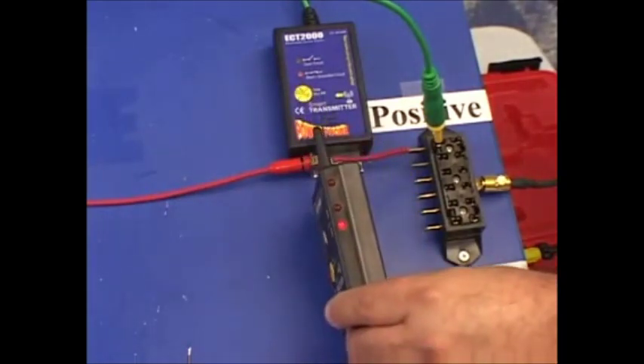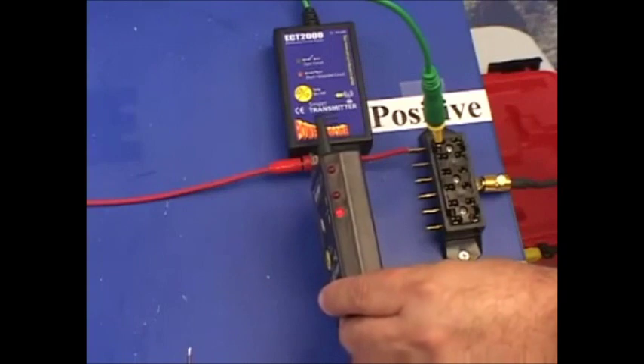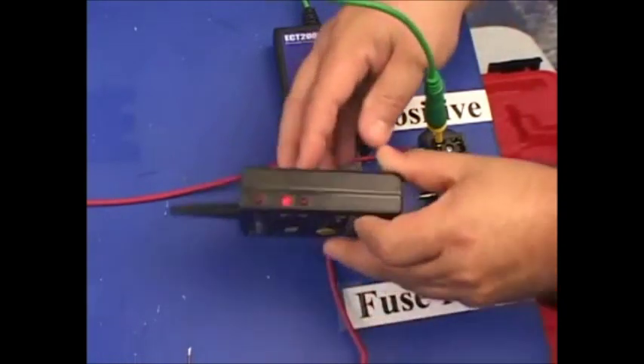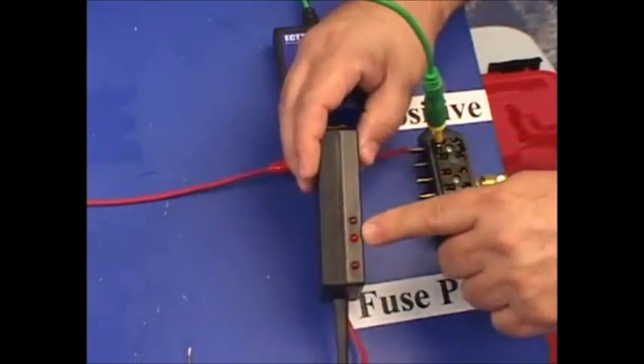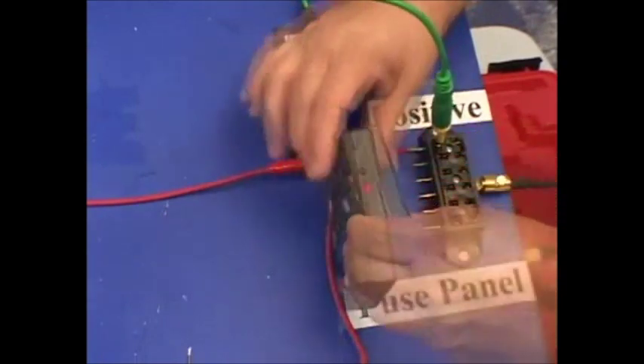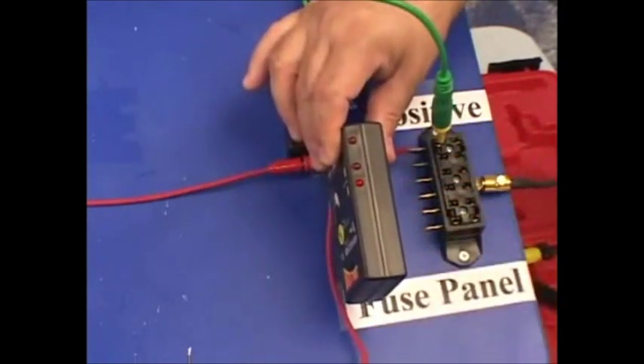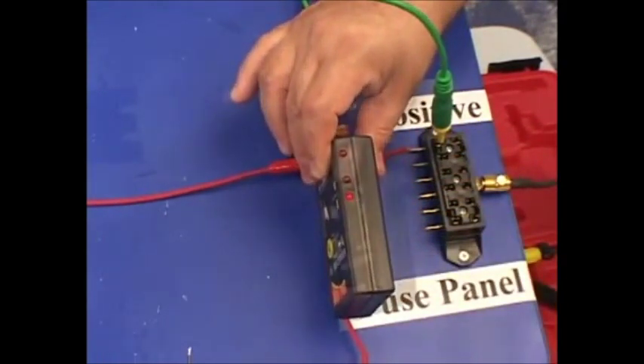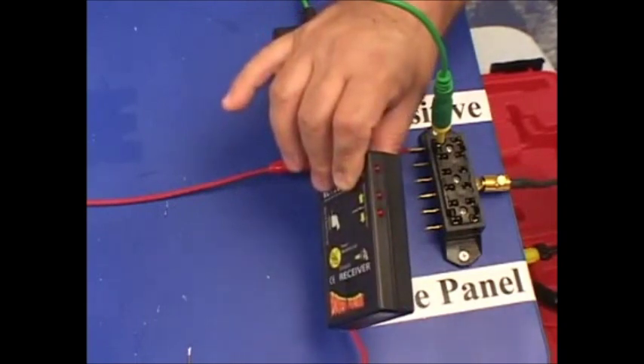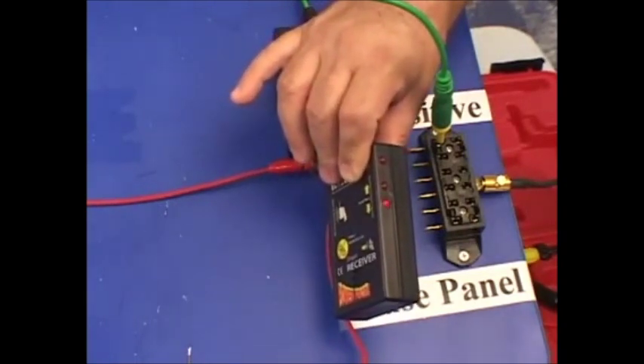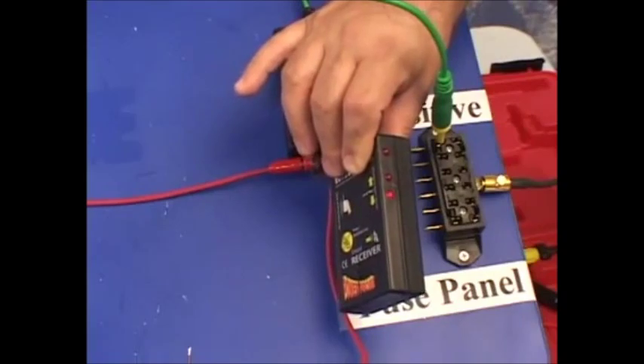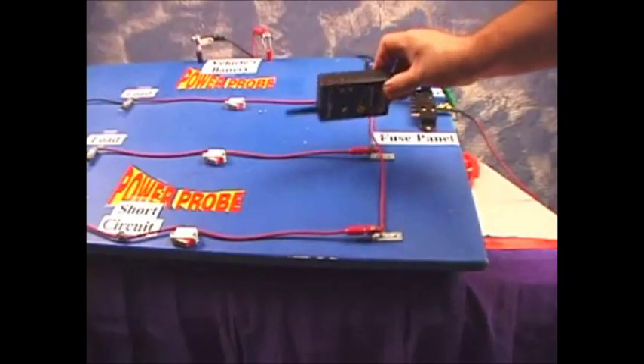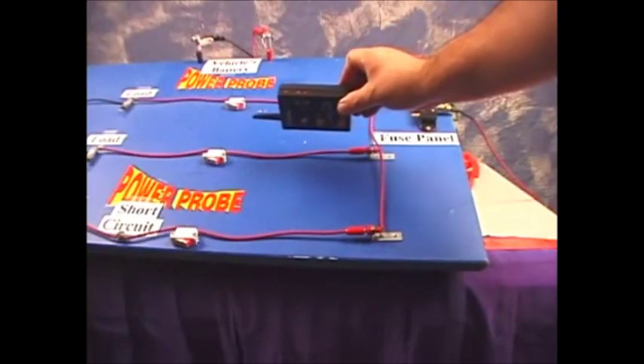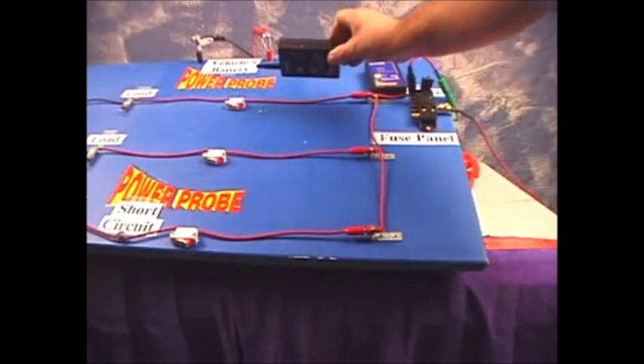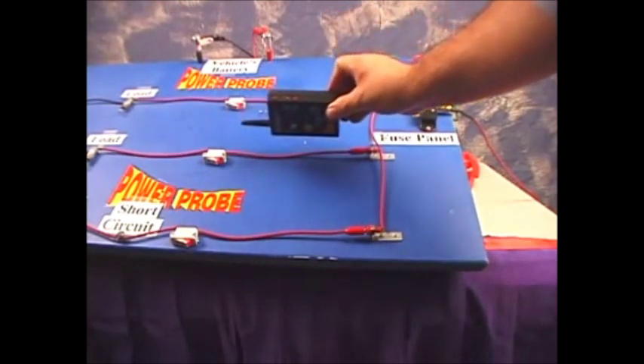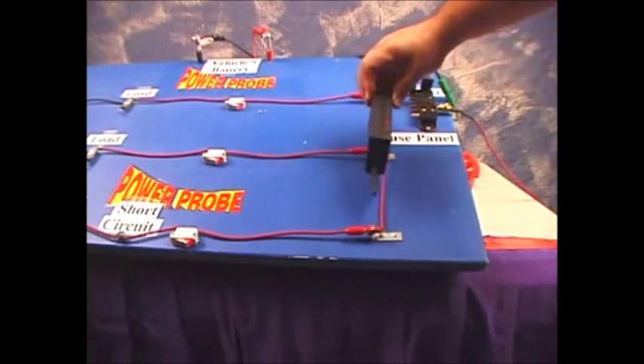Holding the receiver parallel to your circuit in this direction or flip it in this direction, the direction indicator shows you the direction to the short or ground. Now, we don't advocate tracing the circuit in pulse mode. We'd recommend that you lock the reception sensitivity and then trace the circuit. The reason why we want to lock the reception sensitivity is because these parallel circuits are transmitting signals also that we do not want to trace. We want to ignore those signals.